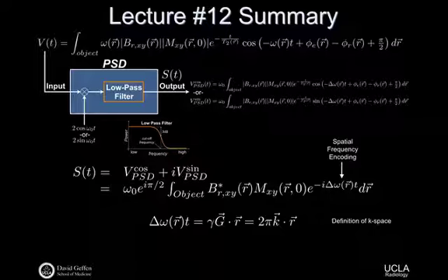Now we had some phase terms which we can exponentiate using Euler's expression, so it ends up looking like e to the minus i times a big phase term that looks something like delta omega, which is a function of space, this is our spatial frequency encoding term, minus the phi from the RF, which could be a function of space depending on how well your transmit coil works, plus some phase from the receiver, which also colors the phase of your measured signal, right? The receiver systems aren't perfect. And then we had this slightly clumsy pi over 2 term, which was just an algebraic convenience. So this is after having combined the two phase-sensitive detected signals, that's all.